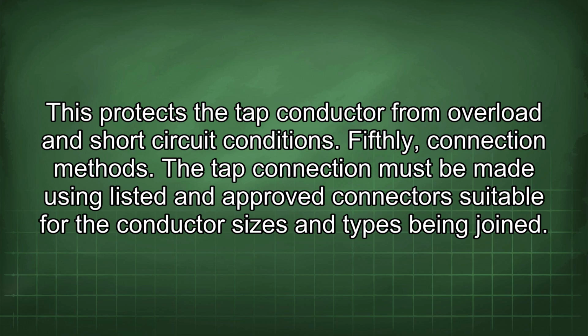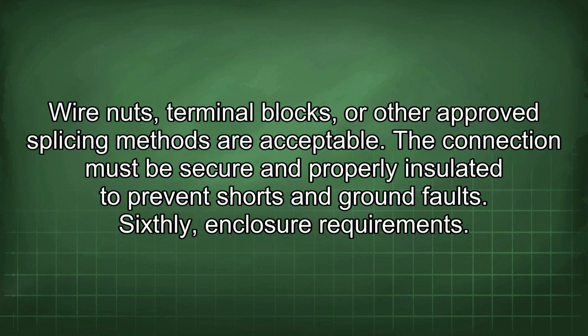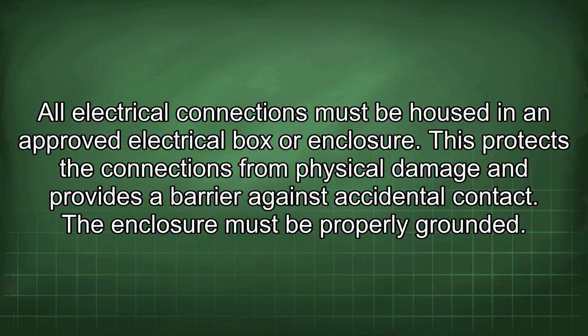Fifthly, connection methods. The tap connection must be made using listed and approved connectors suitable for the conductor sizes and types being joined. Wire nuts, terminal blocks, or other approved splicing methods are acceptable. The connection must be secure and properly insulated to prevent shorts and ground faults. Sixthly, enclosure requirements. All electrical connections must be housed in an approved electrical box or enclosure. This protects the connections from physical damage and provides a barrier against accidental contact. The enclosure must be properly grounded.